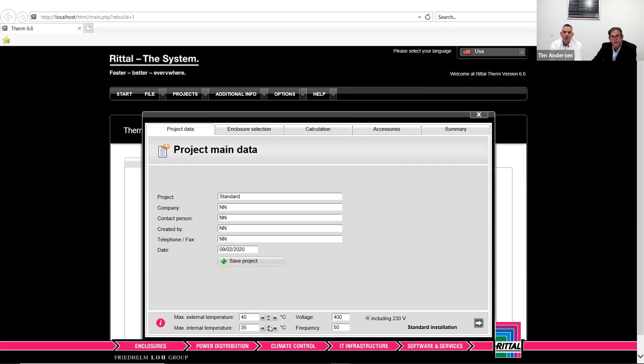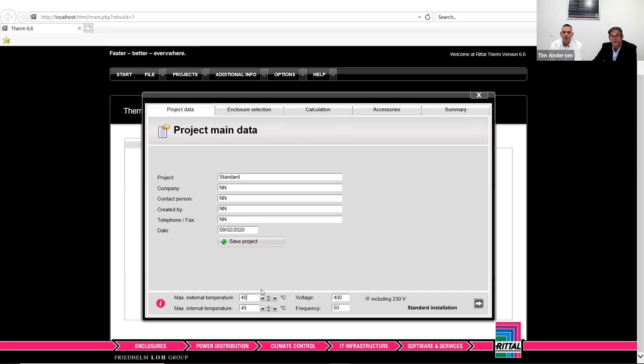So let me explain - we've got the maximum external temperature, that's the maximum ambient plus a few degrees, because it might be 45 degrees in Sydney, but in a typical manufacturing environment they could add 2 or 3 degrees to your maximum external temperature. We're going to use 40 for today. Then we've got the maximum internal temperature of the enclosure. Now these have to be expressed as a difference - if we don't, then we can't use a free cooling method like fans. It's kind of obvious. Also, the difference in temperature here is expressed in kelvins as we go further along. So I picked 40 and 45 in there.